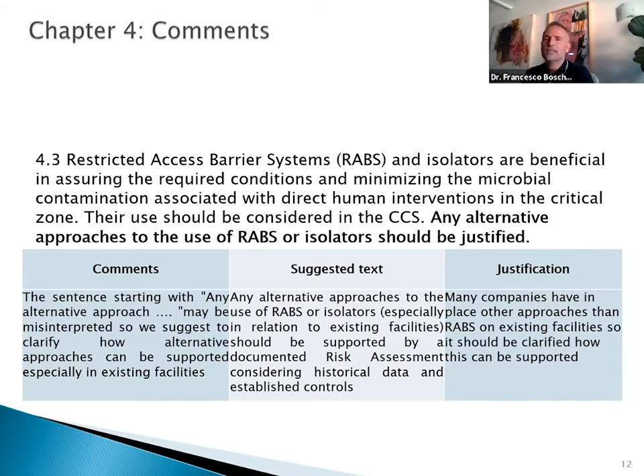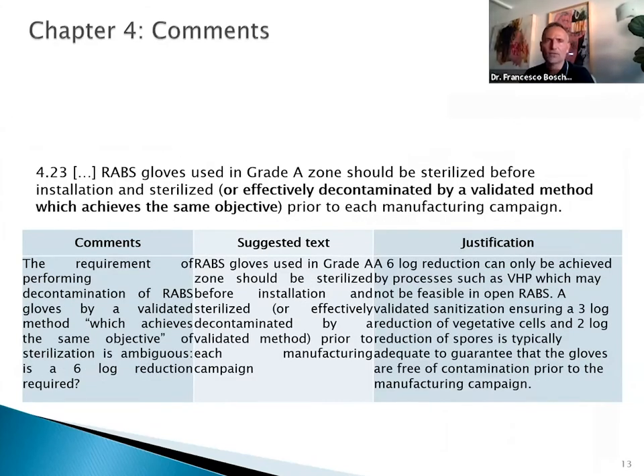So our suggested text was: any alternative approaches to the use of RABS and isolators, especially in relation to existing facilities, should be supported by a documented risk assessment considering historical data and established controls. We tried also to put in some elements that can help different companies write this risk assessment, which is now needed to support any facility different than RABS and isolators, because it's now very clear the annex is pushing the standard towards isolation between the operator and the process, separation more than isolation.